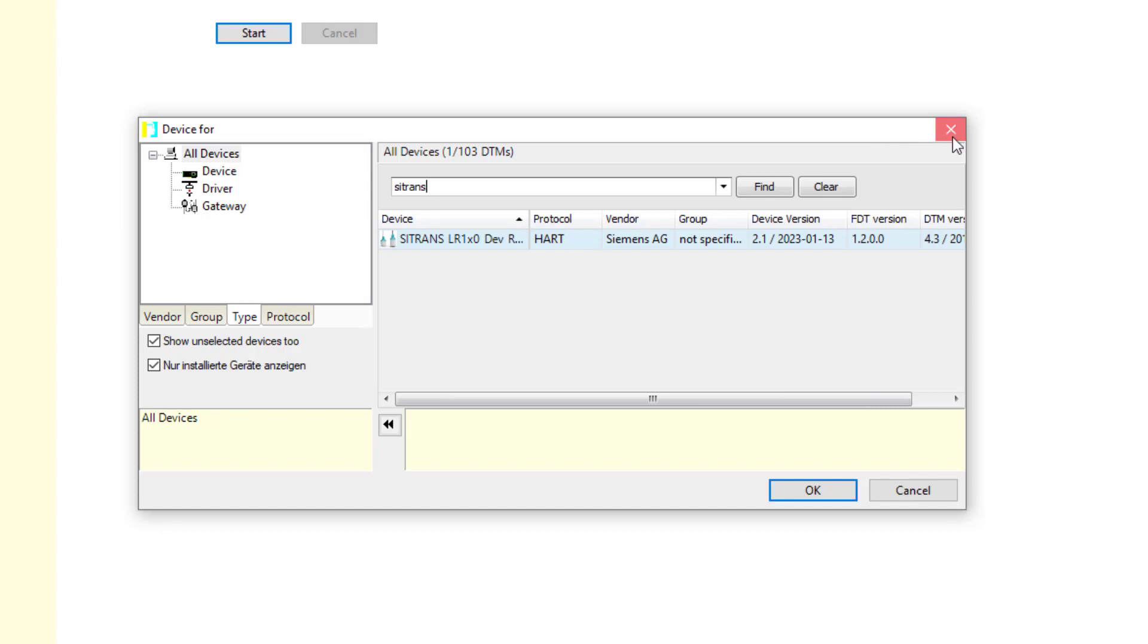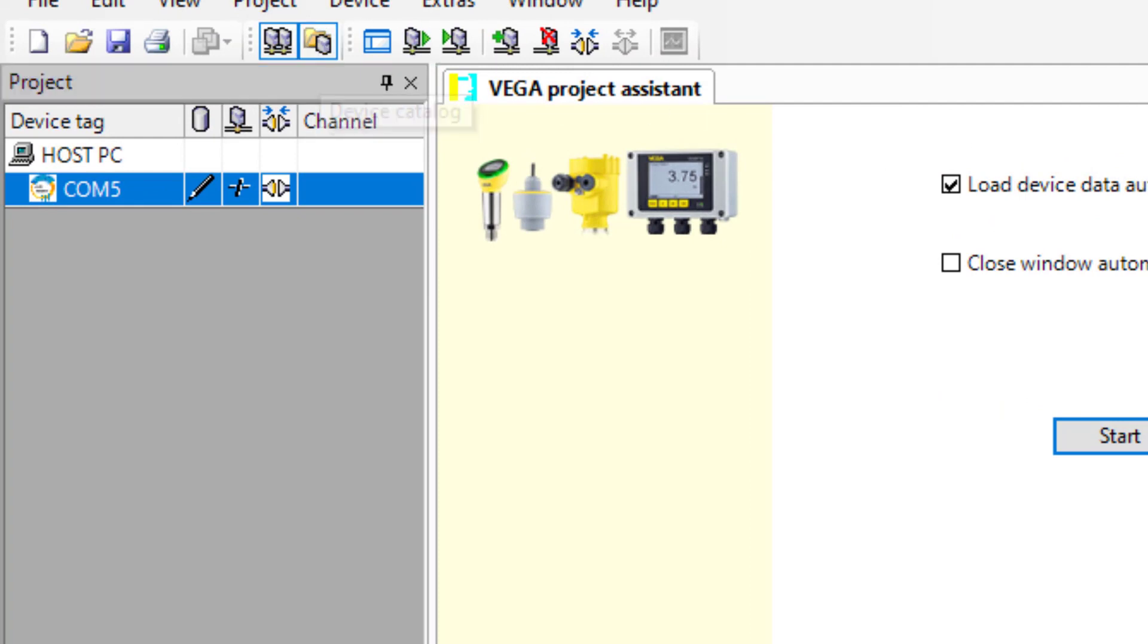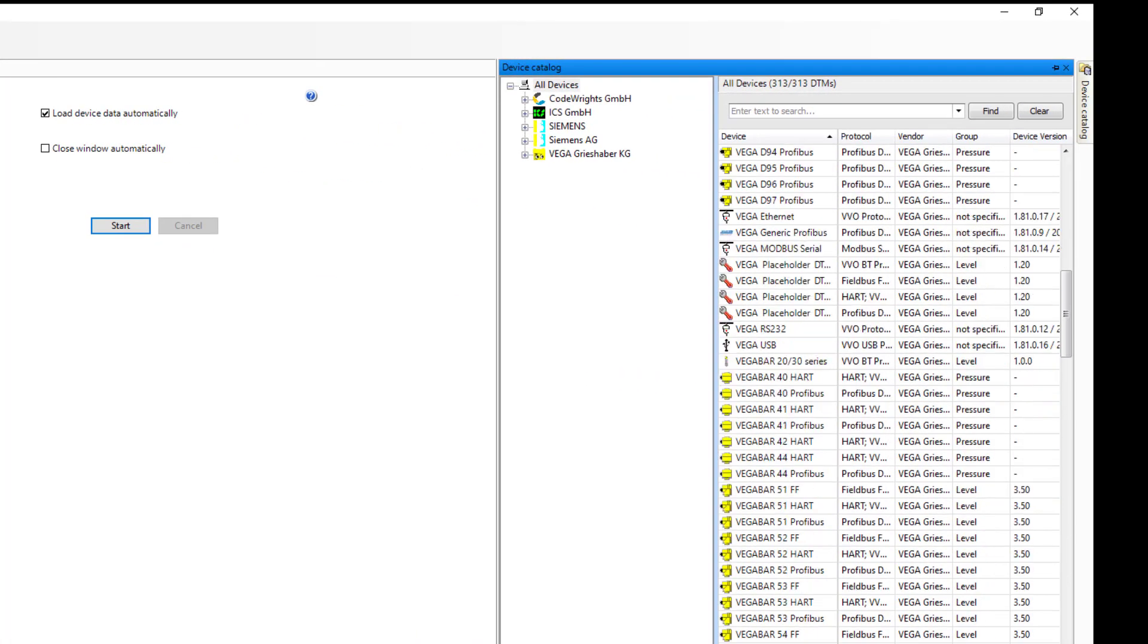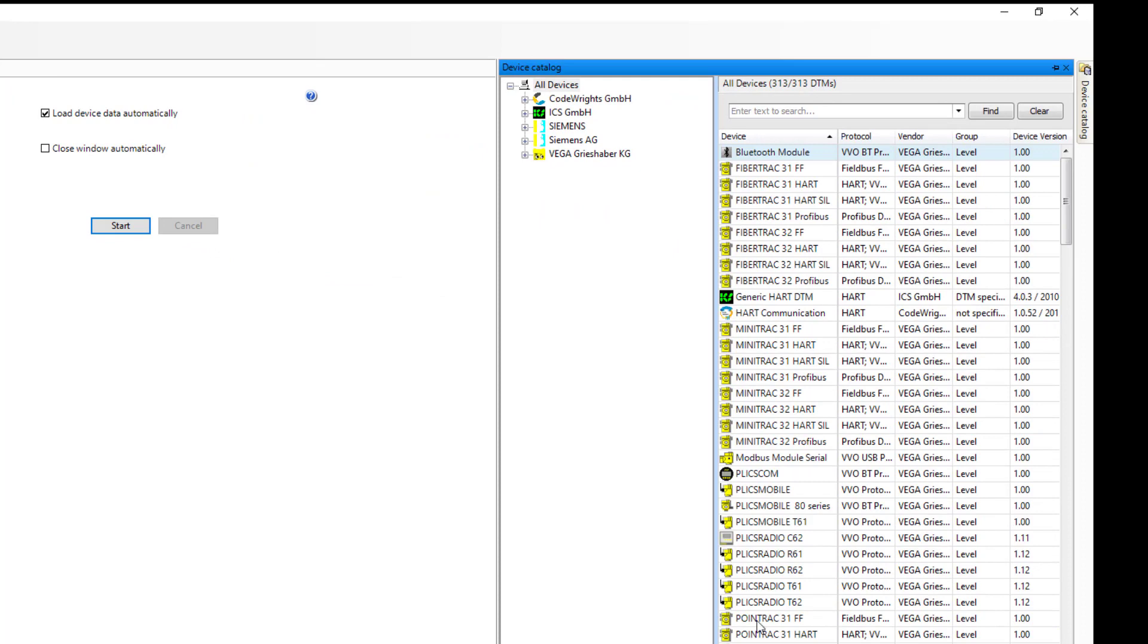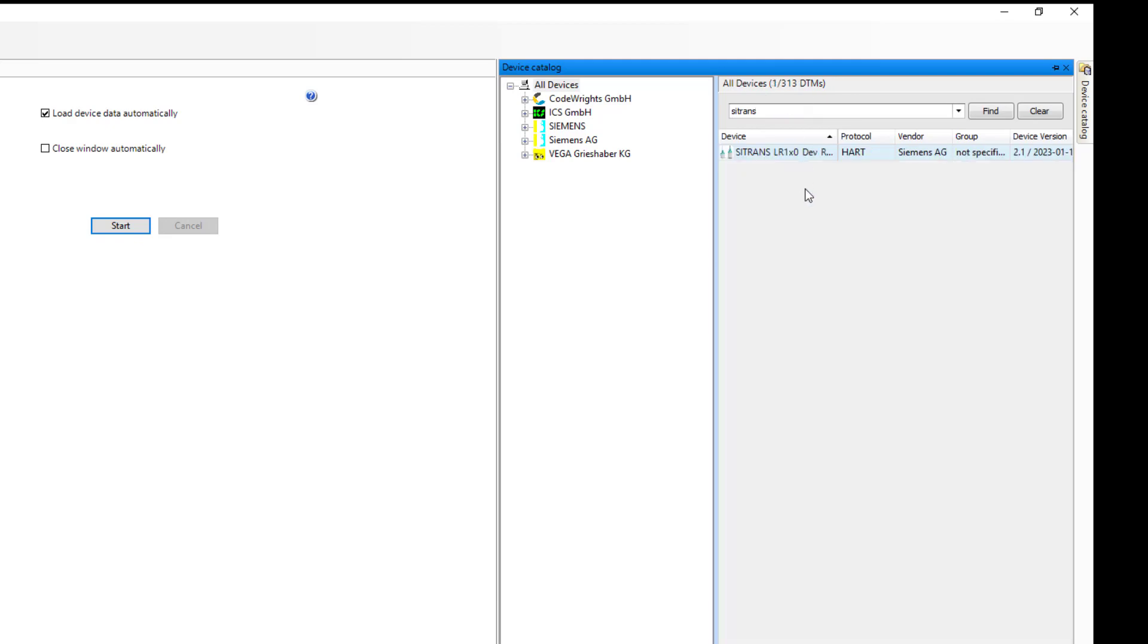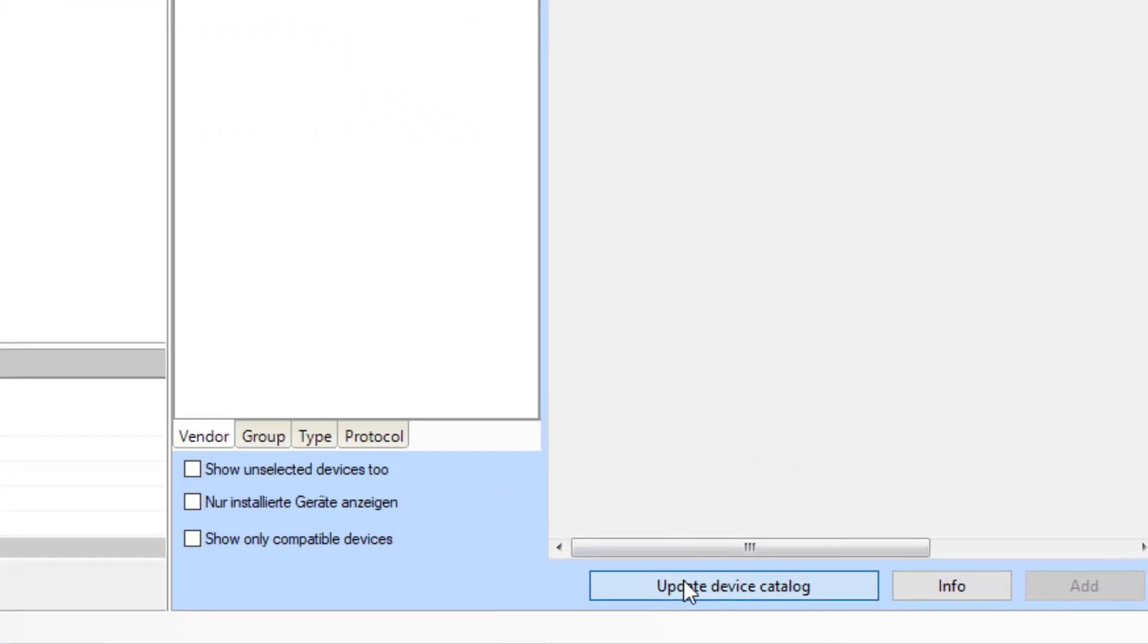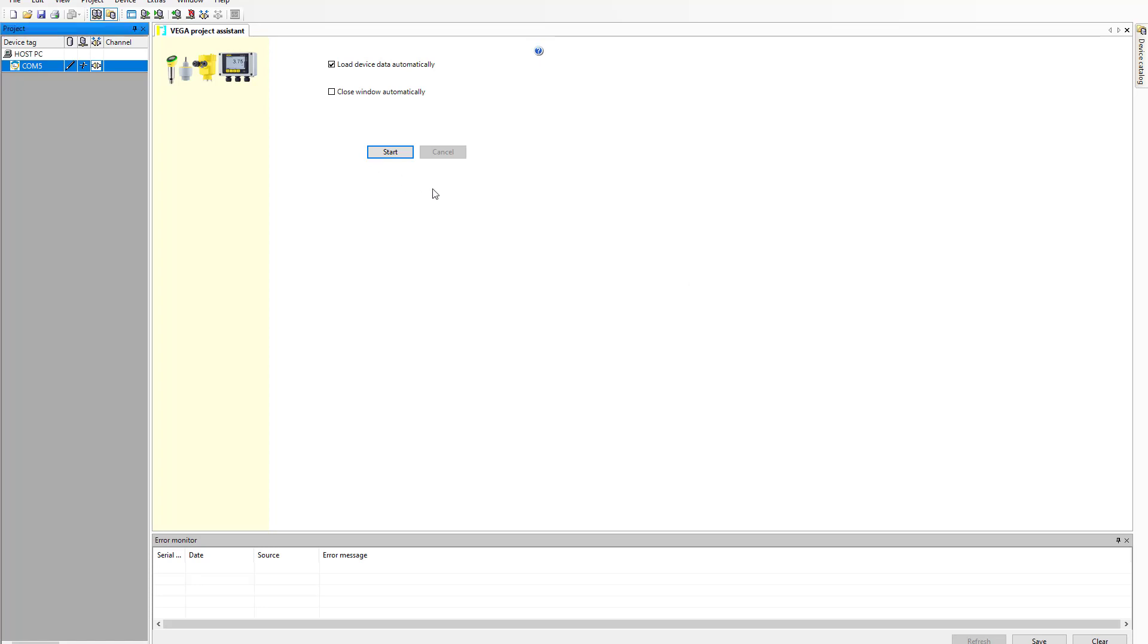I've only got the SITRANS level device, even though I've just installed the DTM. So where is it? And this is the bit that catches everybody out. You have to go back to your catalog and open up the catalog. And then you will probably, let's see if it does it. We'll type in SITRANS again up here. And I've still got the radar. But if I click now on this update device catalog, it's going to pull all of the devices that I've installed via the DTM install file into my catalog.